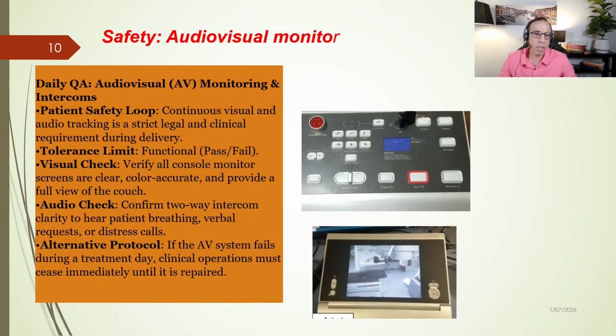Here is a critical clinical rule you must always remember. If your audiovisual monitors or intercom fail at any point during a busy treatment day, you must immediately stop treating patients. Even if the Linac itself is working perfectly, a dark screen or broken microphone means the machine is down until engineering fixes the issue.